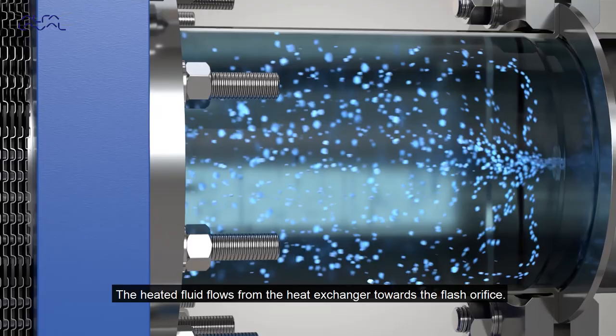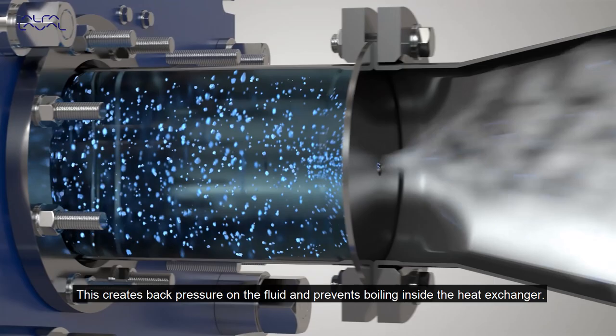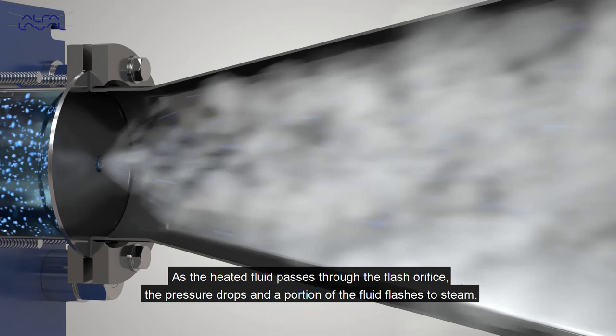The heated fluid flows from the heat exchanger towards the flash orifice. This creates back pressure on the fluid and prevents boiling inside the heat exchanger. As the heated fluid passes through the flash orifice the pressure drops and a portion of the fluid flashes to steam.